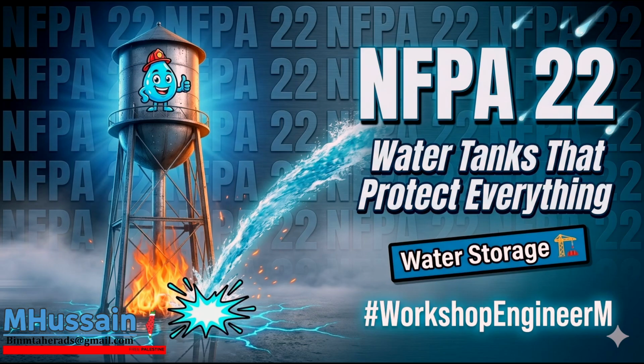A critical detail for the design engineer is that the threads on that manifold must be acceptable to the local authority having jurisdiction, the AHJ. This is where local codes override generic standards. If you design the system with a standard 4.5-inch national standard thread, but the local municipal fire department exclusively uses a 5-inch Storz quick connect coupling, the fire engine physically cannot hook up to your tank. Your hundreds of thousands of gallons of water are completely locked away while the building burns, just because of a threading mismatch.